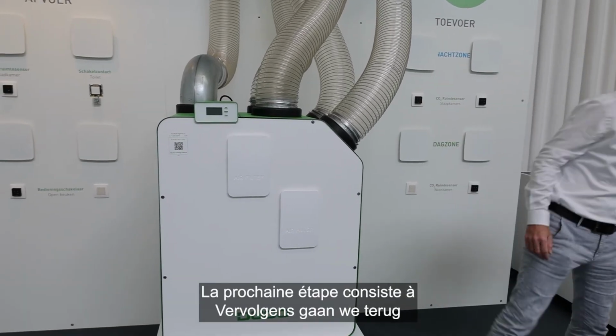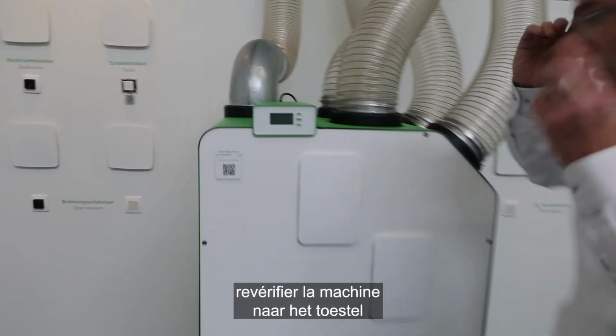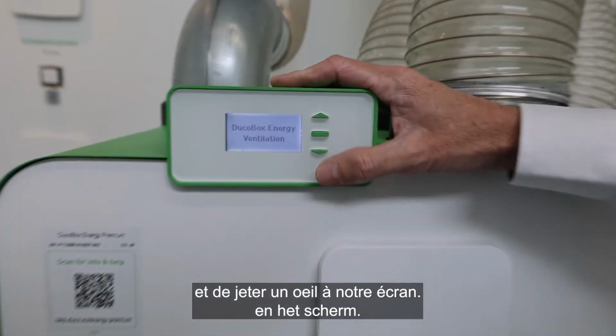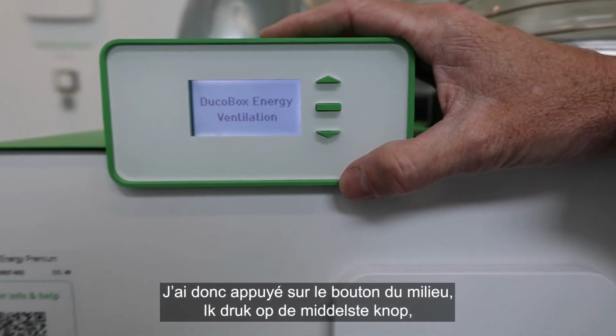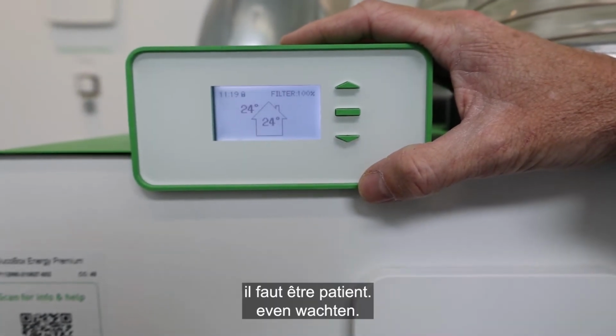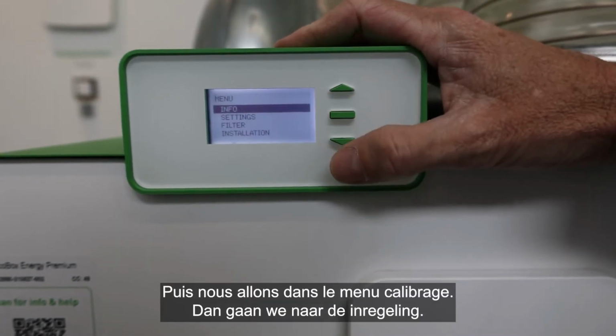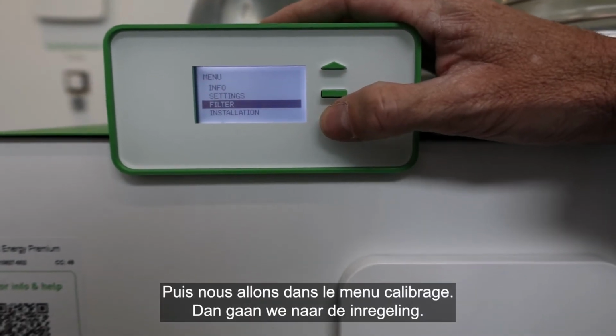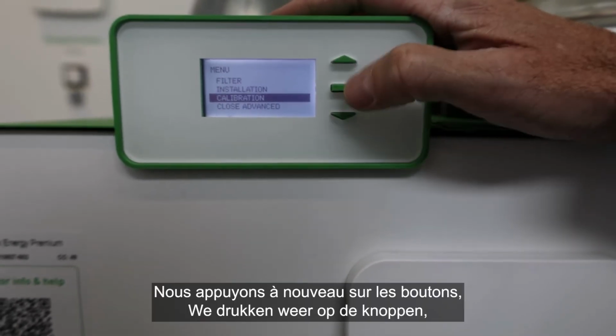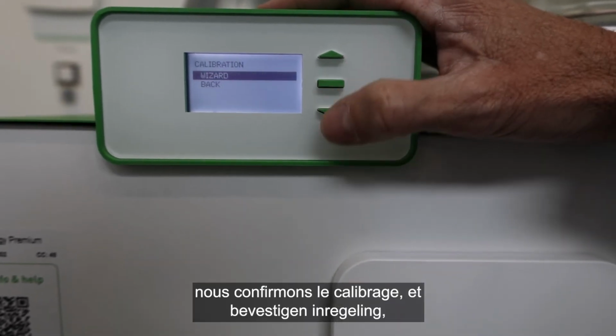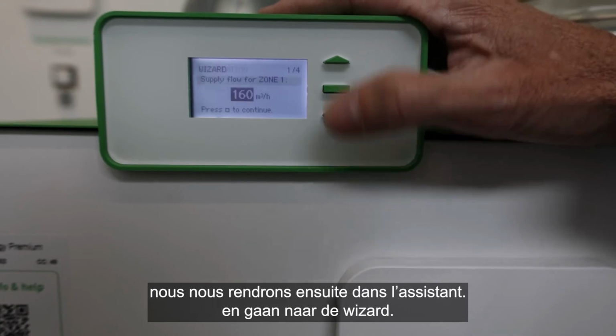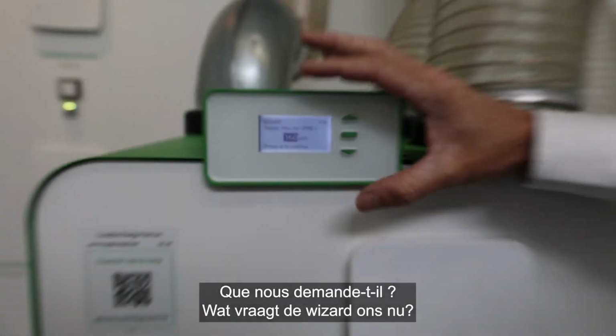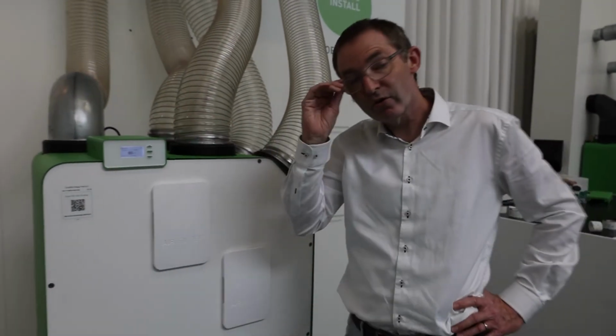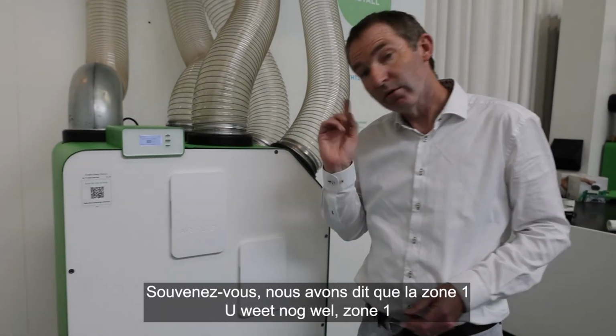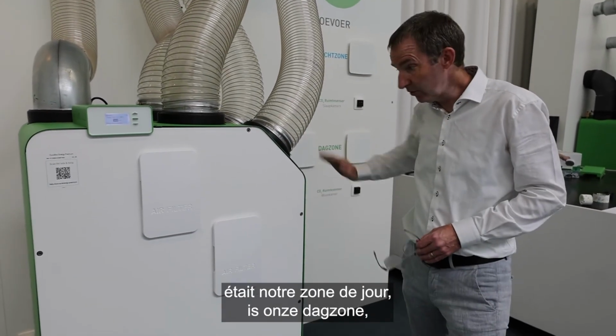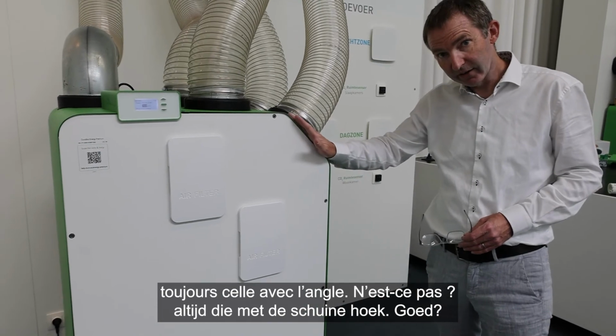The next thing to do is to look at the machine again and look at our display. I just push the middle button, give it some time, and then we go to the calibration. Here we go, we just push the buttons again, confirm calibration, and we need to go to the wizard. What does the wizard ask us now? The wizard asks us, what is your required airflow in zone 1? Remember we said zone 1 was our day zone, always the one with the angle, right?